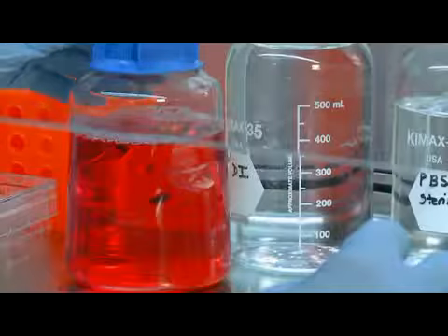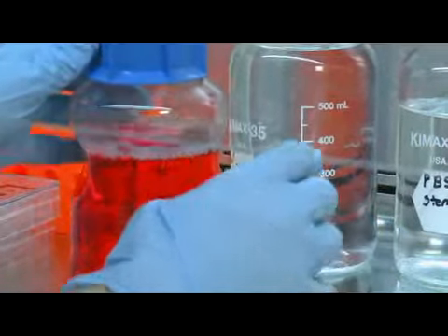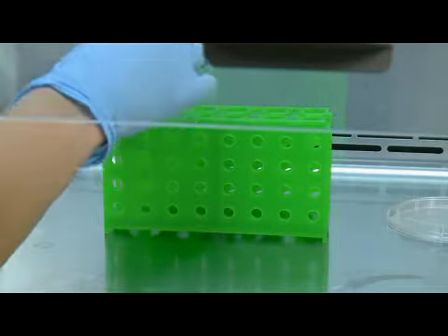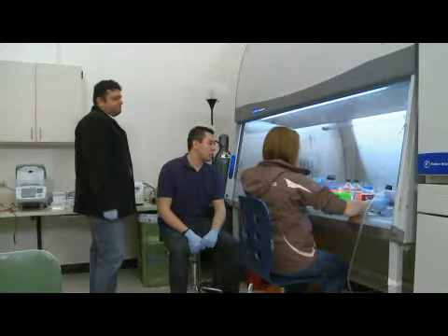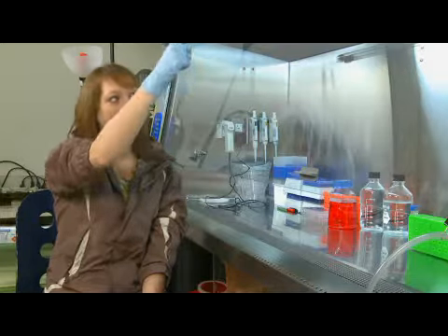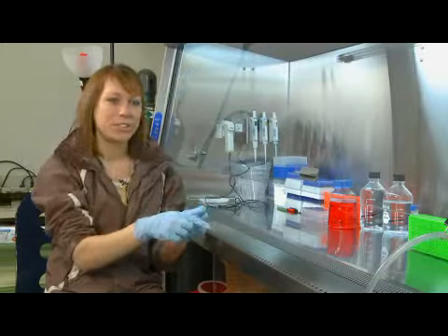disease state. This is our Biosafety hood. We do all of our sterile procedures in here, so when we're culturing cells, when we're changing our media, we all do it in this hood. So that air actually comes down from the top and then it flows down and out to the sides. That way your samples don't get contaminated with anything else that's in the hood.